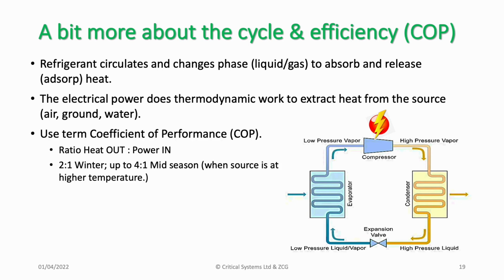The term coefficient of performance is used, and this is the ratio of useful heat out to power in. So in the winter, I would expect a minimum coefficient of performance of 2 to 1. So I get 2 kilowatts out for 1 kilowatt in. And if the ambient conditions are higher, then that coefficient of performance rises.